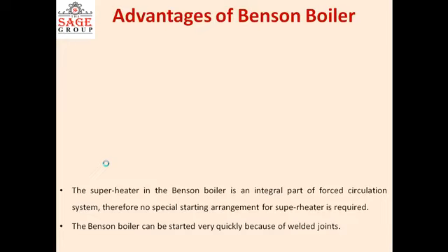One more thing, because no boiler drum is used, the parts can be taken directly to the site and assembled there. The superheater in the Benson boiler is an integral part of the forced circulation. Therefore, no special starting arrangement for the superheater is required, and the Benson boiler can be started very quickly because of the welded joints.